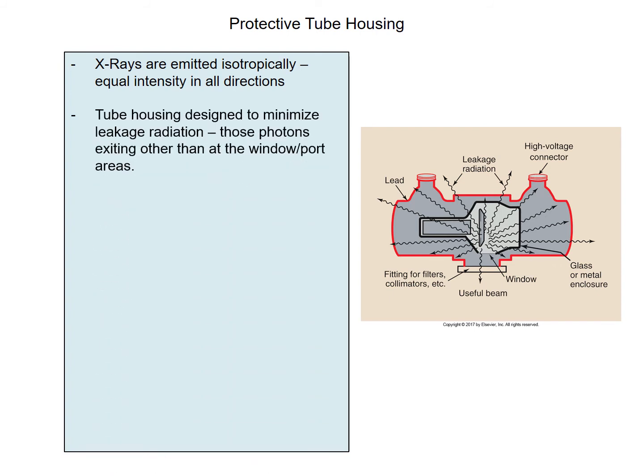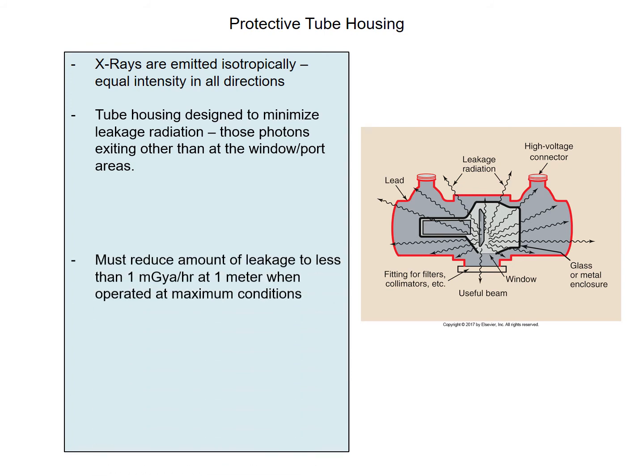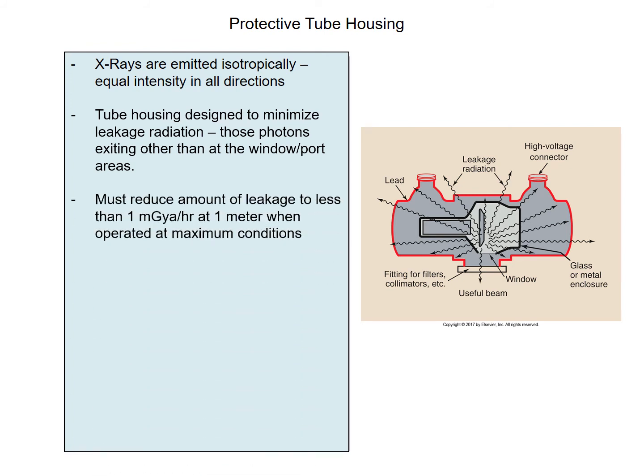So the tube housing is designed to minimize this leakage radiation, because sometimes photons do get through the housing, and those of course are called leakage. Those are the photons that exit other than at the window of the tube or the port of the housing itself. By law, these tube housings must reduce the amount of leakage to less than 1 milligray per hour at a distance of 1 meter when operated at maximum conditions. That is a fact that you want to make sure that you remember for the registry. Protective tube housings must limit the amount of leakage radiation to 1 milligray per hour at 1 meter.